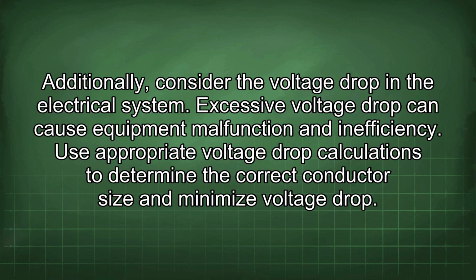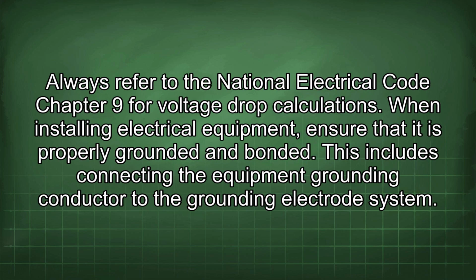Additionally, consider the voltage drop in the electrical system. Excessive voltage drop can cause equipment malfunction and inefficiency. Use appropriate voltage drop calculations to determine the correct conductor size and minimize voltage drop. Always refer to the National Electrical Code Chapter 9 for voltage drop calculations.